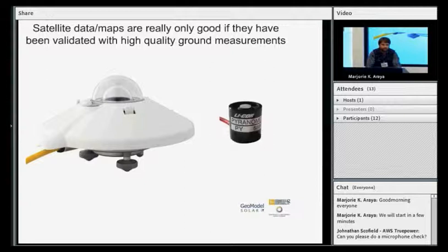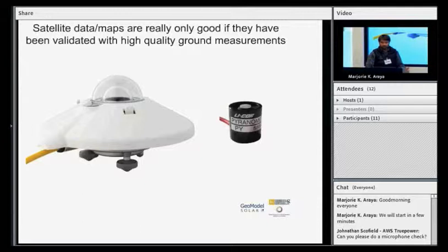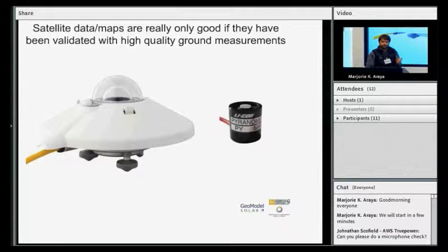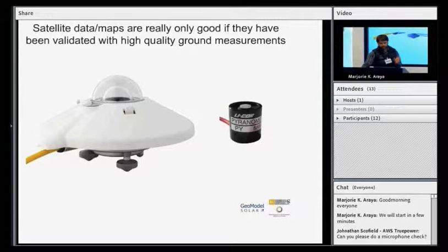So here is an example of two typical solar instruments measuring global horizontal. The one on the right-hand side is about $300, and it's typically used in weather stations, amateur weather stations, and also, unfortunately, by a number of weather stations in developing countries. It's got a daily uncertainty of about plus-minus 5%. Now, as Harsh mentioned, satellite data is already sometimes better than that, so you want an instrument that's more accurate. On the left is an instrument with a daily uncertainty of plus-minus 2%. That's kind of the best you get from these instruments, and that's what you want to aim at. This instrument is about $3,000. If you start adding up the cost of preparing your site, installing your instrument, the other equipment, sending someone to install it, the cost difference goes away. So I really want to promote the use of very accurate measurement instruments.